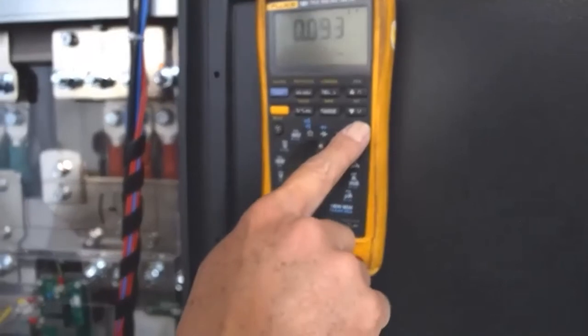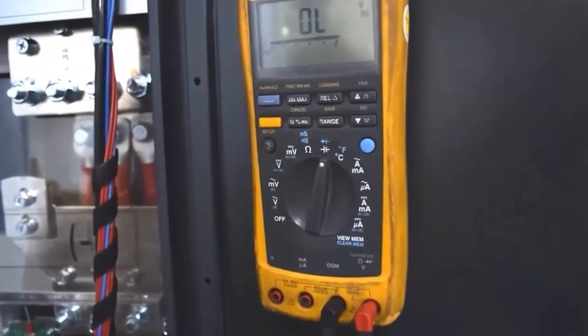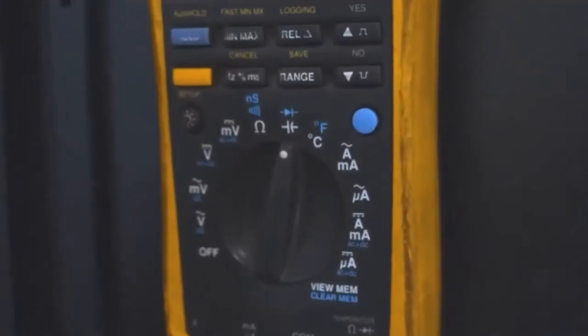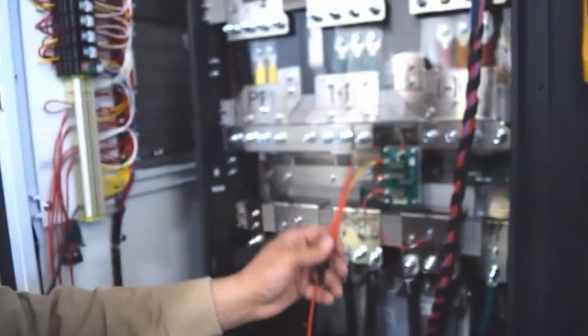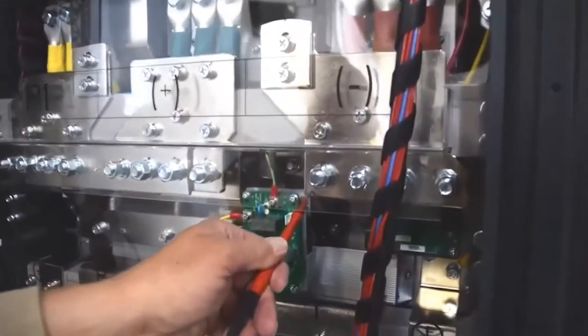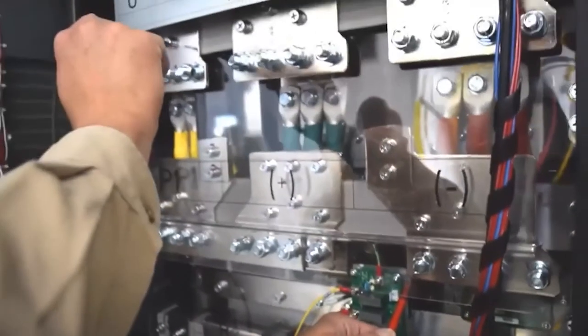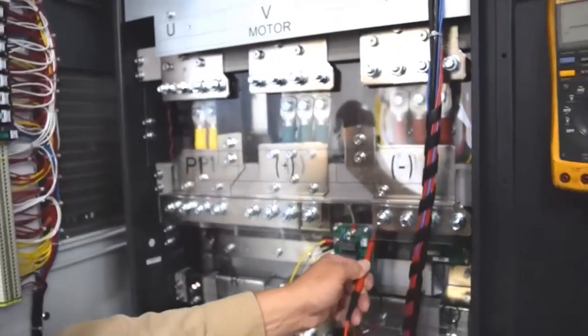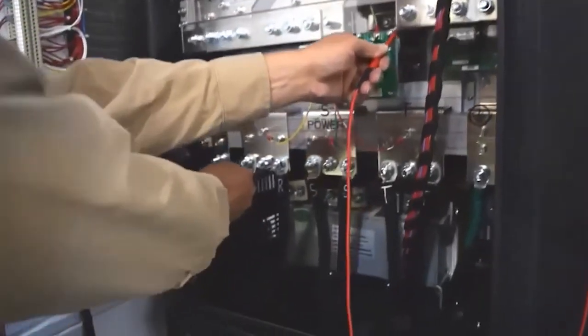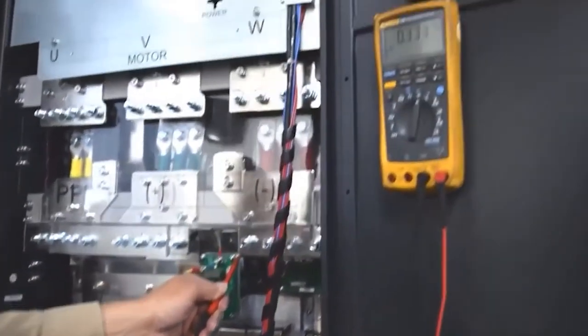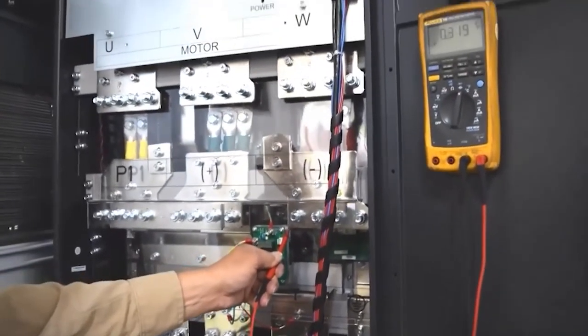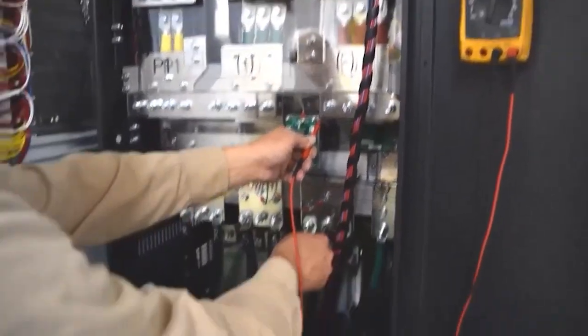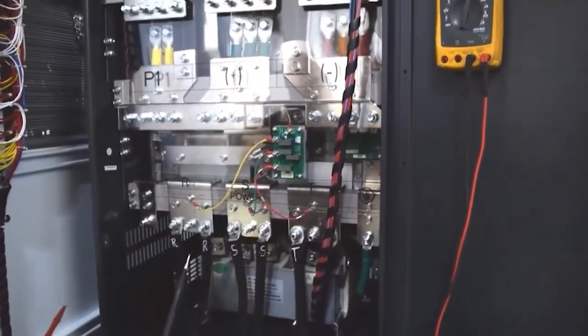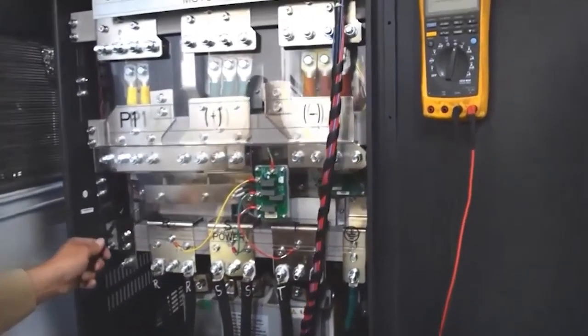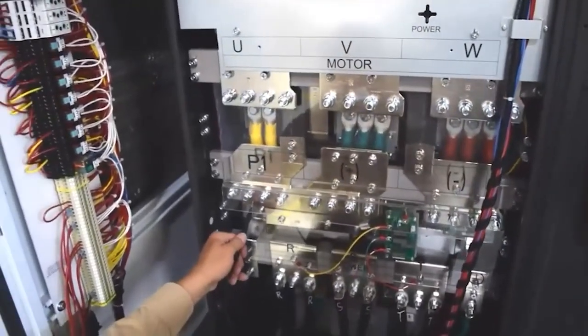Then I'm going to put my meter in diode mode, which is the little blue arrow on my meter with the line in front of it. I'm going to take my positive lead, find my negative bus and put it on it. And I'm going to measure all my inputs, which are down on the bottom. I should get a reading that's about the same all the way across. In this case, I had a 0.33, 0.312, and 0.32. Pretty normal readings, all within tolerance.